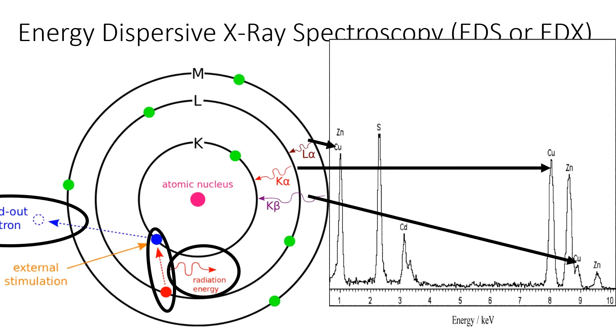Spectrum patterns are then related to a library of spectra to determine the elements present. Elements are then weighted and an elemental composition can be found. A single spectra is called a point scan. Multiple points can be put together to create line scans or area scans at the expense of time and or accuracy. Area scans are very useful tools and are often used to produce compositional maps to further describe microstructure. You'll see this more and more as you go on through the term. Each element will be represented by a specific color. The longer the scan was taken for, the image will be more complete, accurate, and useful.